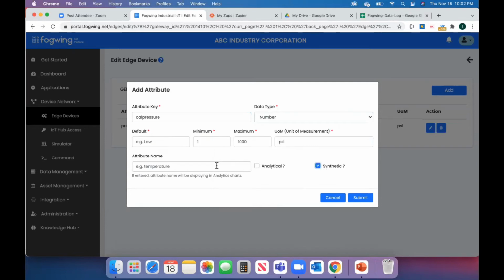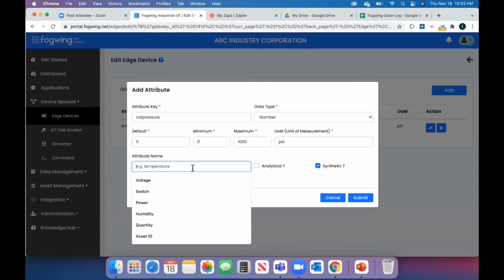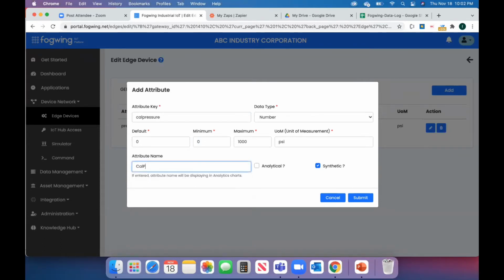So I'm declaring this as a synthetic attribute. If you declare it as synthetic, you need to define it with a default value of 0, and then set the minimum to 0 and maximum to 1000, for coil pressure.